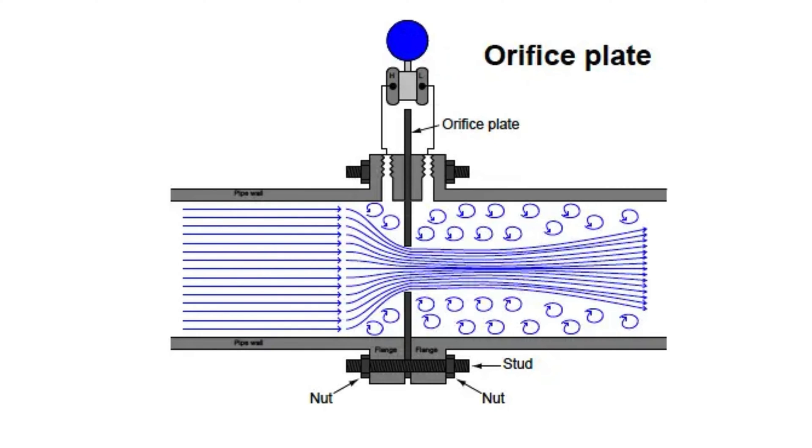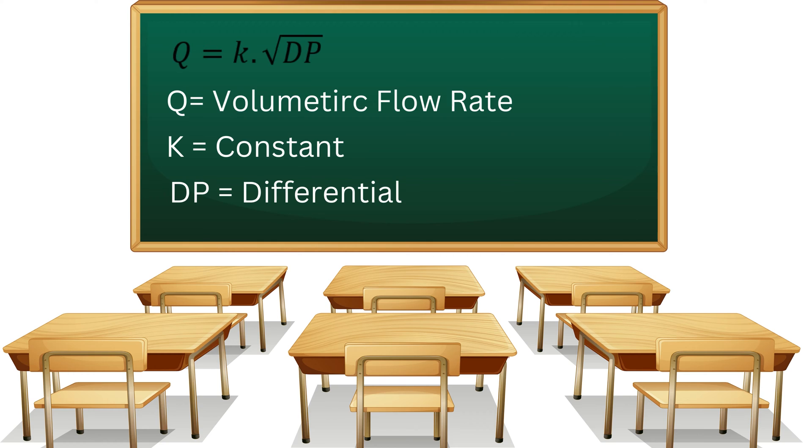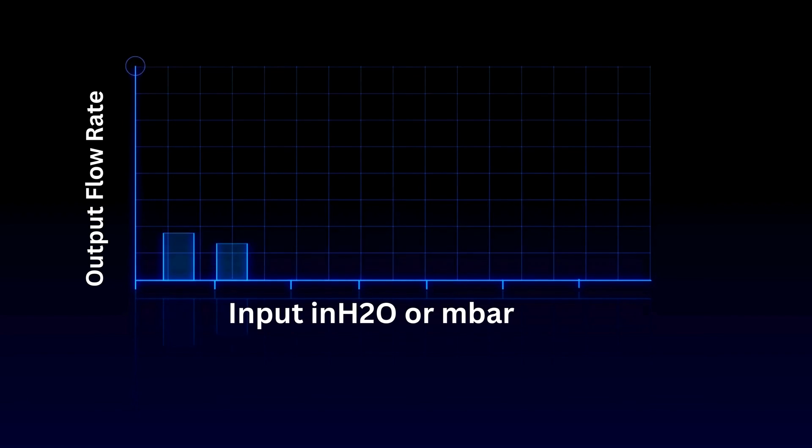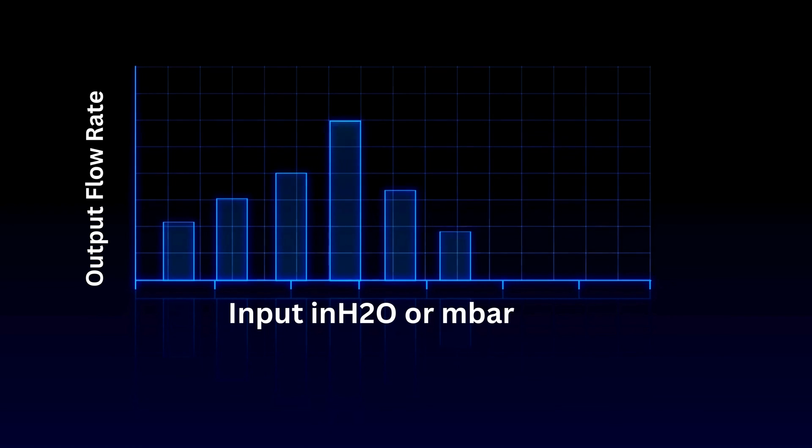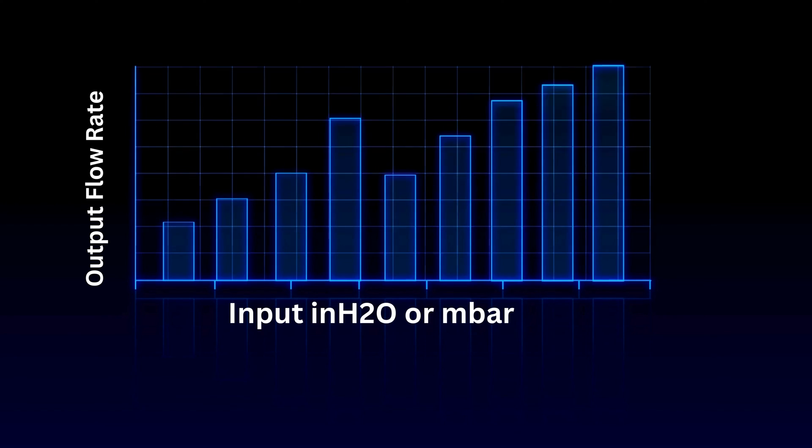Relationship between flow rate and differential pressure: Q equals K multiplied by the square root of DP, where Q is the volumetric flow rate, K is a constant, DP is the differential pressure, and the square root function represents the relationship between velocity and pressure. From this equation, we can see that an increase in differential pressure will result in an increase in flow rate. However, the relationship between flow rate and differential pressure is not linear but square rooted.